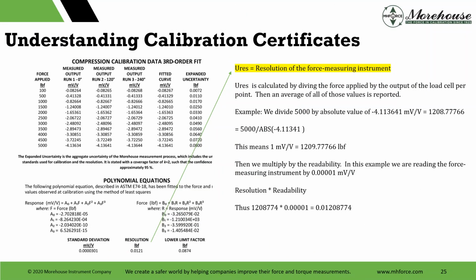This is U resolution, the resolution of the force measuring instrument. It's calculated by dividing the force applied by the output of the load cell per point. Then an average of all those values is reported. So if we wanted to do this longhand, some people say, how do you get this resolution down here? How do you get the 0.0121?